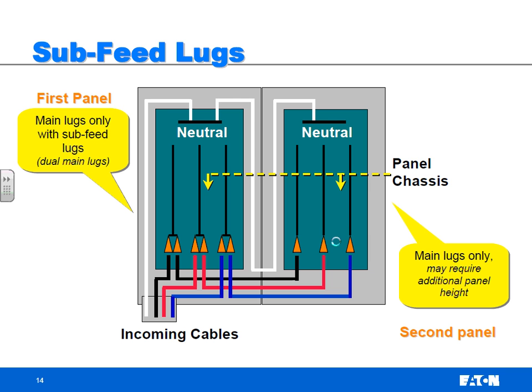For sub-feed lugs, your first panel on your incoming cables has main lugs, not a circuit breaker. And then the main lugs, you can daisy chain. This is basically a double set of main lugs, so you can daisy chain to the next one. So the power of both panels flows through their individual chassis and connects at this point right here on the lug to go upstream.